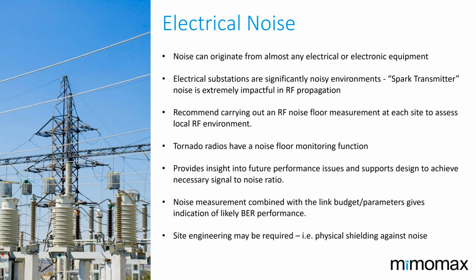With switching transients, since it's often a very fast transient, if you consider the Fourier transform of that, you've got a very broadband noise source. If you start to point your antenna into that switch yard, it will generally receive all of that energy, given these are broader beam antennas. So that's just something for consideration when looking at electrical noise in these environments.